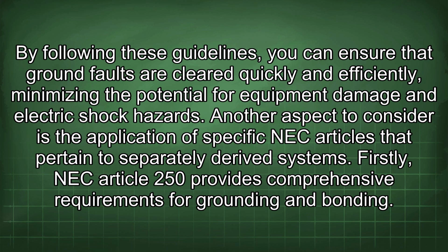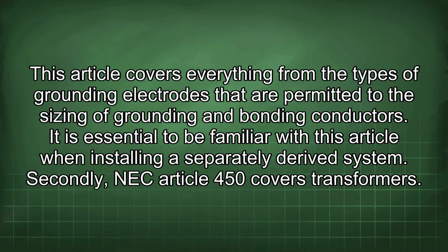Another aspect to consider is the application of specific NEC articles that pertain to separately derived systems. Firstly, NEC Article 250 provides comprehensive requirements for grounding and bonding. This article covers everything from the types of grounding electrodes that are permitted to the sizing of grounding and bonding conductors. It is essential to be familiar with this article when installing a separately derived system.